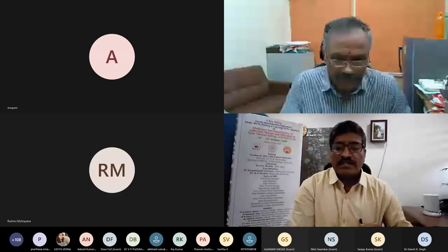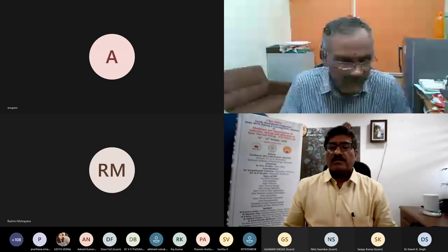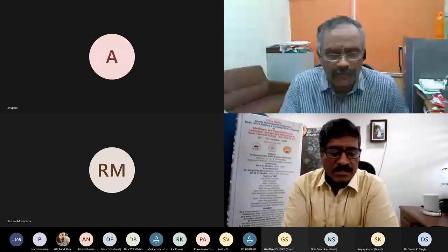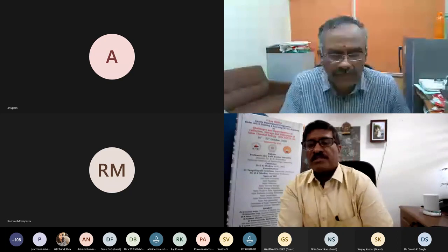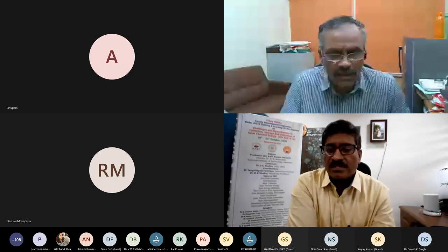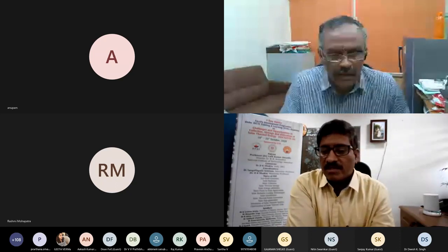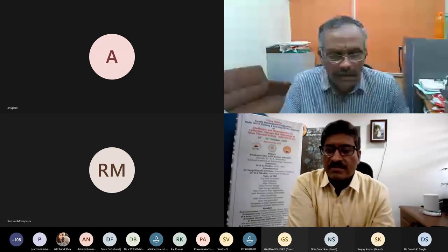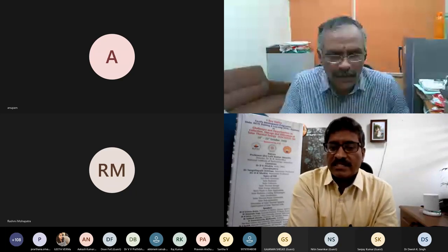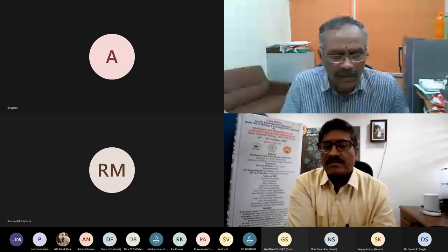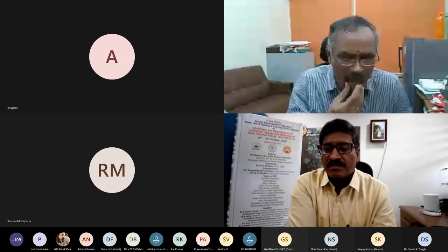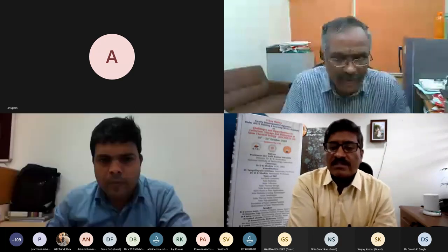Sir, I want to add one point on these cooling towers. Okay, please go ahead. One of the elements in poly generation is the desalination system. Recently, some industry people approached with a challenge and some solutions, especially for the evaporation losses from the cooling towers. There is a desalination technology, a water cycle, where air can be humidified and then followed by dehumidification, like condensation. Because they already have hot water, if they apply this humidification as well as dehumidification for a cooling tower, they can recover the water.